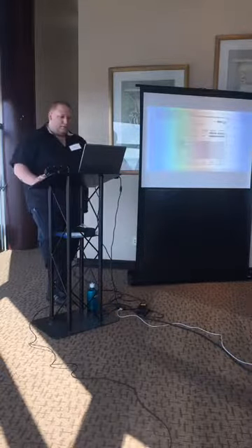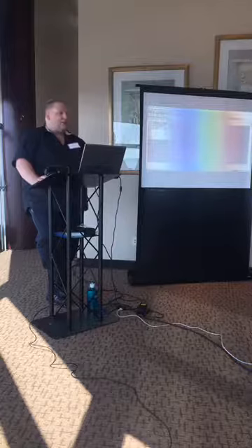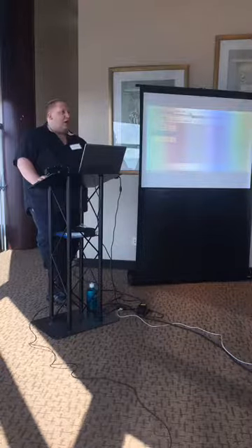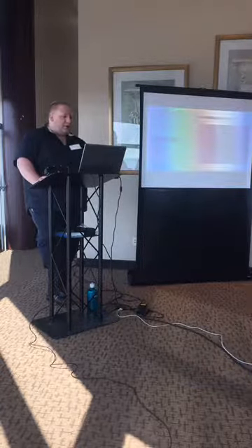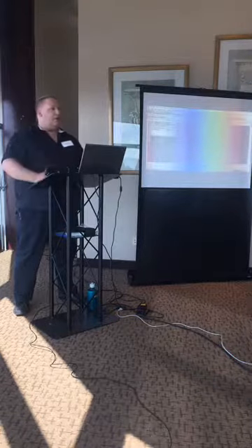So when I go to run the model here, I can go to my cost report. And as you can see, when you use control valves, your costs are going to be a lot higher than if you were to just use a VFD. So here I've saved a couple $100,000. And so that's an example of how you can show the savings by using VFDs.